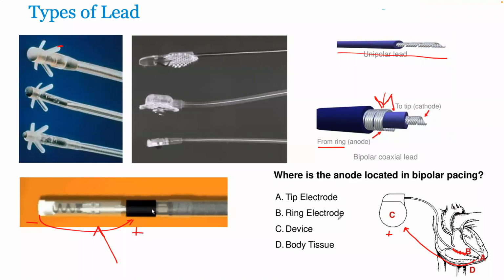But the other instance, which is probably worth bringing up, is especially at implants, maybe for an operator or even the rep or the physiologist in charge of testing the devices. When you think there's an issue of perforation, we're typically programmed tip to ring here. And sometimes if you do have lead perforation, then usually your tip electrode has come out of the myocardium. But because your circuit with the ring electrode is so short, you can still capture enough myocardium with enough output. If there's ever an issue that you have perforated, it's always worth programming the device to unipolar tip to can. And if you get no capture, then that is probably evident that the tip electrode is outside of the myocardium.